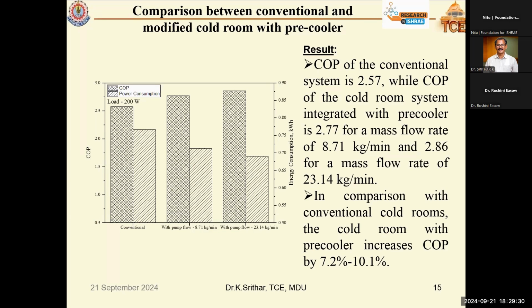It gives only 2.57 for conventional, whereas we have an increase in COP to 2.77 at the lowest mass flow rate, and when we increase the mass flow to the highest value, we got the highest COP of 2.86. So the net result is that when we use the highest mass flow rate of water in the pre-cooler, the conventional cold storage COP increases from 2.57 to 2.86. That is the first outcome, about a 7 to 10% increase for various flow rates. That is the graph shown.